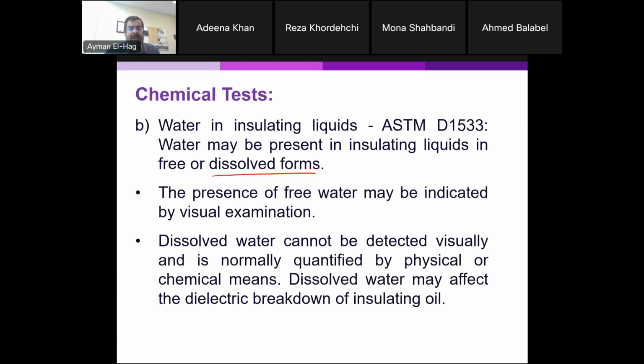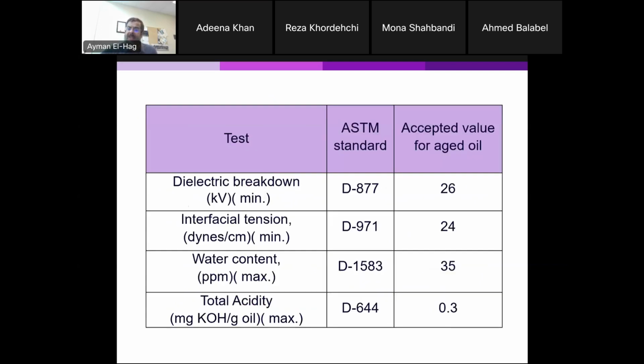Now, does dissolved water affect the dielectric breakdown? Yes, it will. If you have higher water content, then the breakdown definitely will go down. But the water content is one of the very sensitive tests, more sensitive than the dielectric breakdown. These are some typical accepted values for aged oil, not new oil.